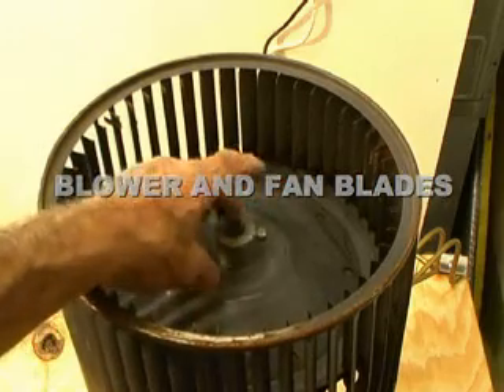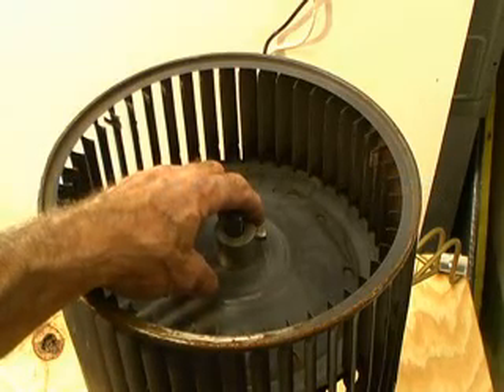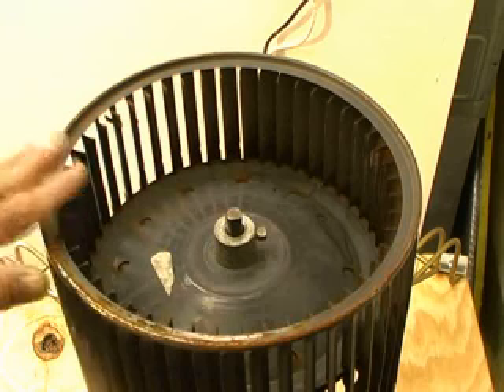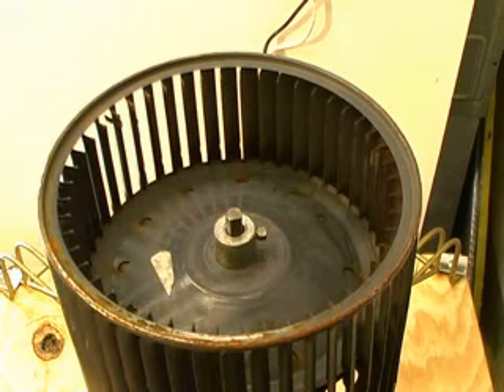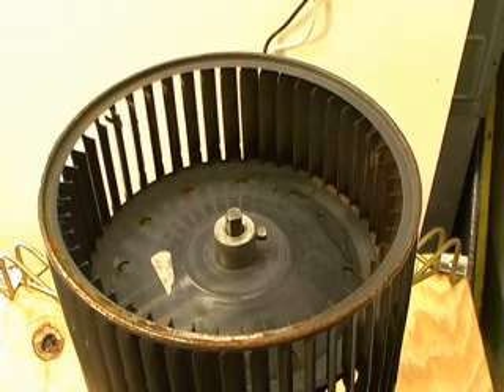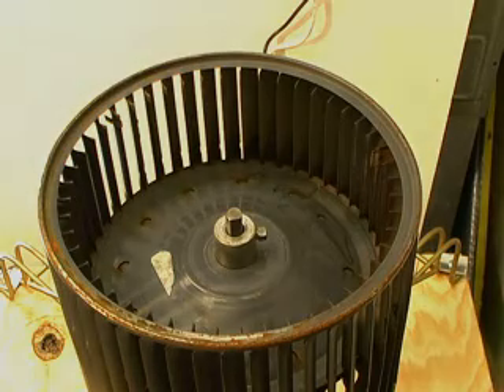I went on a package unit one time and I turned it on, and just a few seconds after it started up, the motor, what I thought was the motor, would start making a sound. It sounded just like one that was messed up, making a grunt and growling sound. I went and got a new motor, came back and put the new motor on it, turned it on, the same thing. Then I got to looking close.